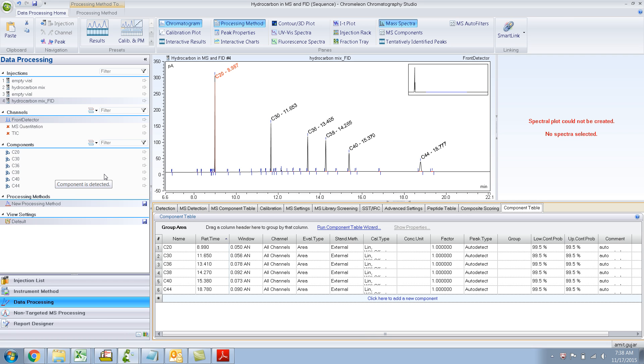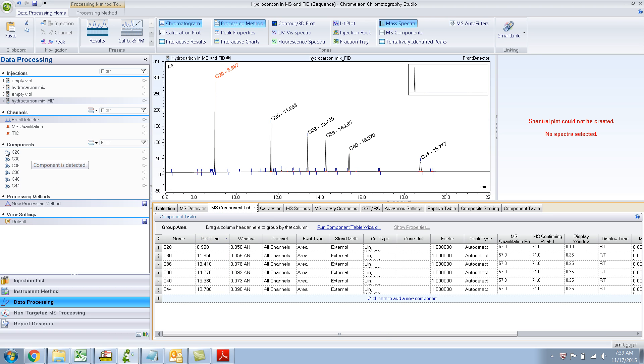Generally, the way I use the mass spec and FID - if I have FID, especially for hydrocarbons - I will use the mass spec for confirming that we have a hydrocarbon, but I'll use the FID for quantitation, because it's easy to use and it's very popular for hydrocarbon analysis since it has a large linear range and all the good stuff that comes with FID. Hopefully you got some idea about how to look at the components, and if you have MS components with exclamation marks or crosses, you got an idea of how to fix that problem.